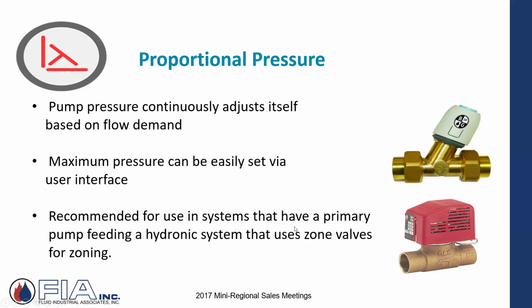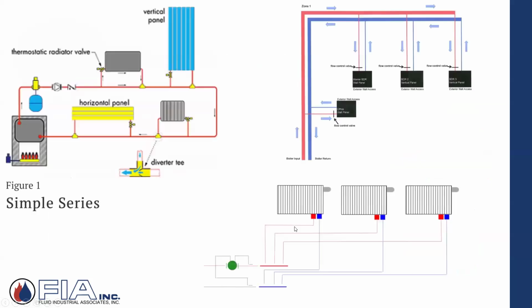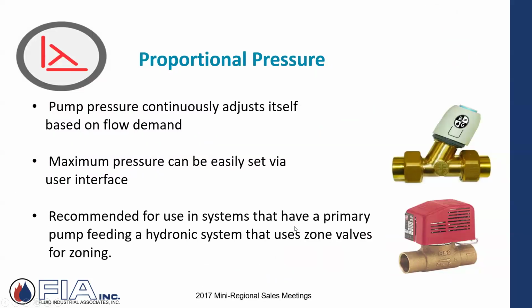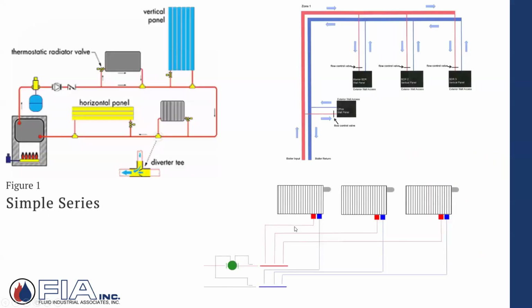And where the utilities want or are interested in funding some incentive is I've got speed control. As I reduce the speed, I reduce the kW, the amount of energy this pump is using to heat or cool that space. And it's all happening right on board simply by selecting this mode and dialing in a set of conditions. So all we're trying to show here is, okay, what is a proportional pressure mode? What does that look like when you have a primary pump in a hydronic system and it's using zone valves? Well, it could be a lot of different things.